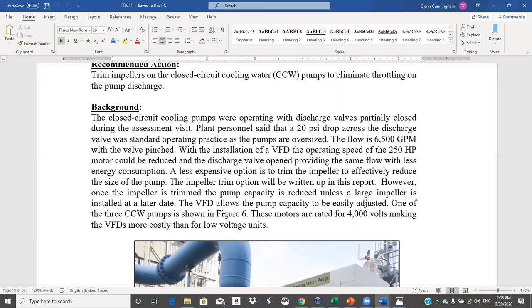And times 0.746, we'll give that in kW. So that's about 87 kW. And we've got 3 pumps. So there's a good chance you could do that with an impeller trim. Take the pump apart, take the impeller to the machine shop, get the pump people to tell you how much to machine off, polish it back up again, put it in, open the valve, and you get the same flow, and you would save that loss across the valve.